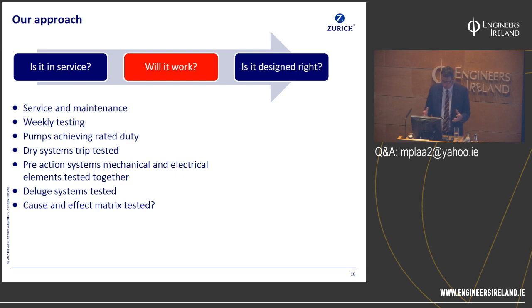Is there a maintenance contract in place? Are the pumps being weekly tested if it's a pump-based system? Have you got evidence to support that? Are the pumps achieving rated duty? Well, I still find the service engineer filling in his service and maintenance sheet with figures that are made up. When I've gone to physically flow test the pump, my figures and their figures from the last service do not match. So it's important that those tests of the pumps are done: are they meeting the requirements, and is the hydraulic demand checked?